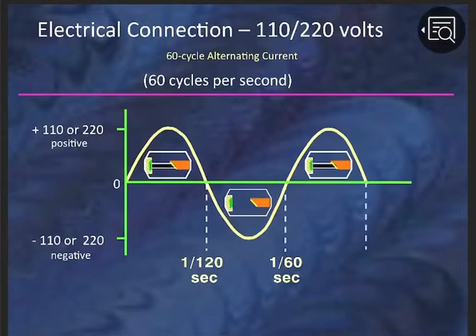Suppose I keep the exposure time at 1 second. For the whole 1 second the X-rays are generated. Whereas for alternating current, only for half, 0.5 seconds, X-rays will be generated, and for 0.5 seconds there will be no X-rays. That is the disadvantage of using alternating current. So what the manufacturers do is change the alternating current to a direct current, and then the machine works on direct current. The advantage is less patient exposure. Now if this is clear, we'll move on to the tube head.